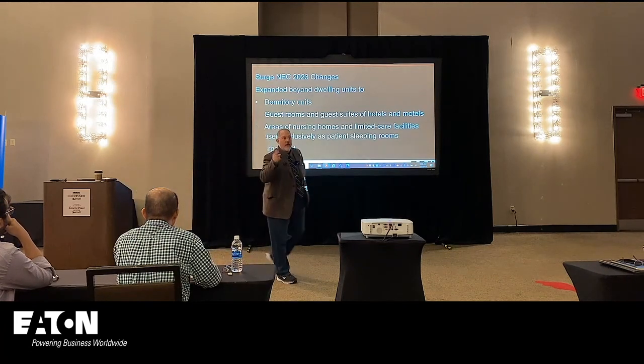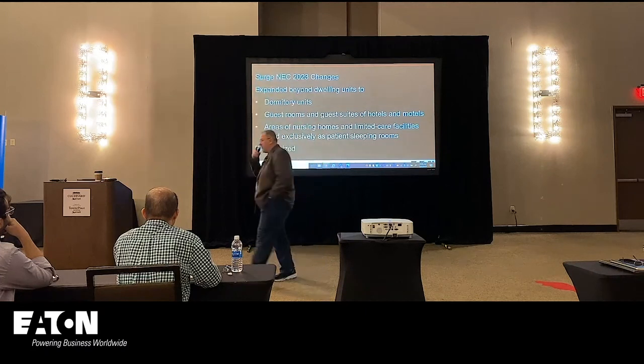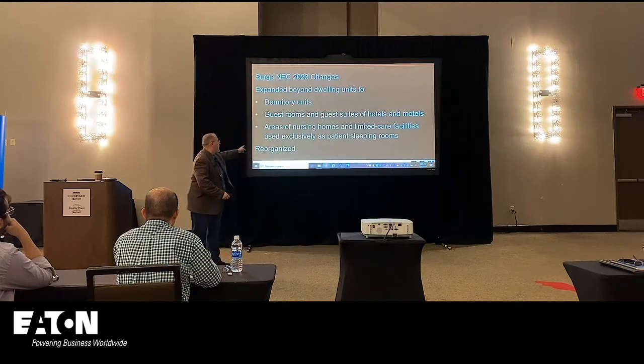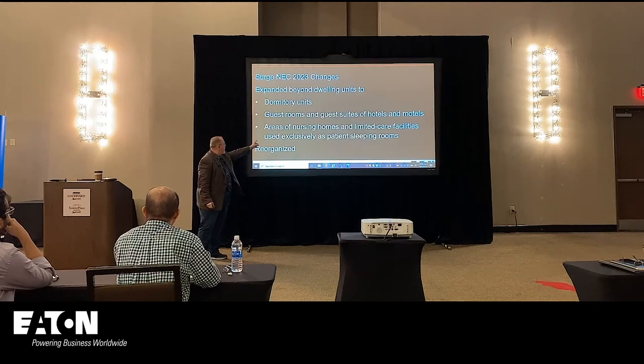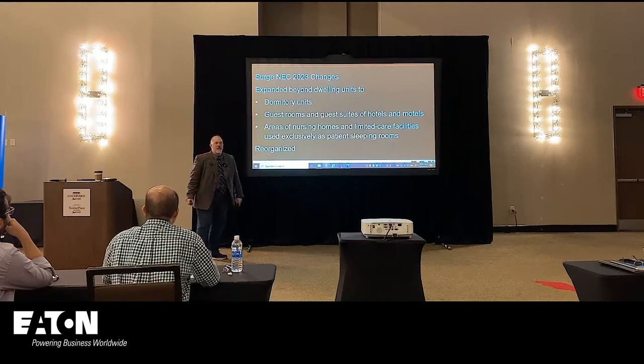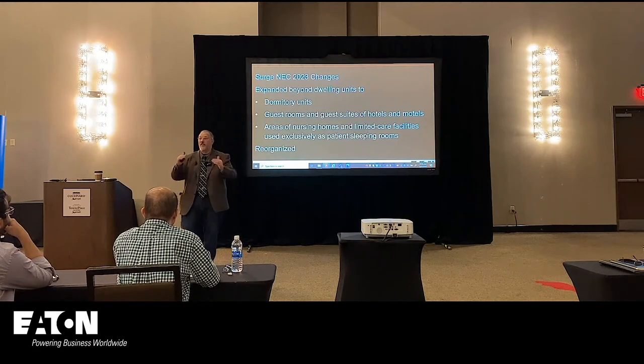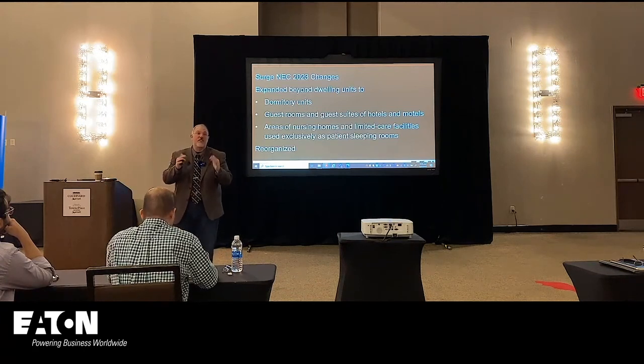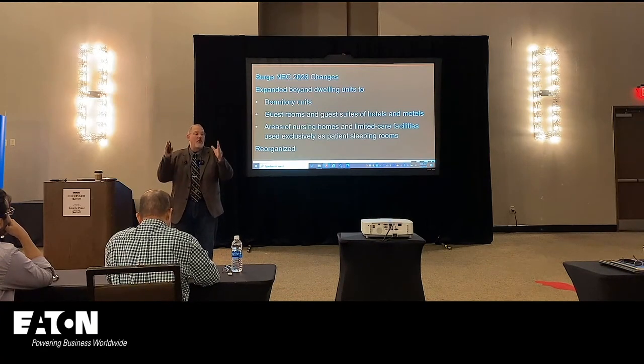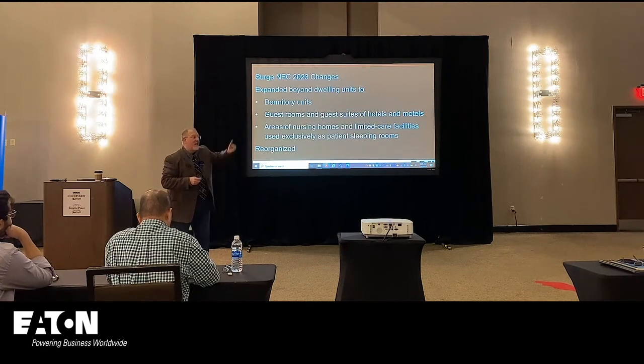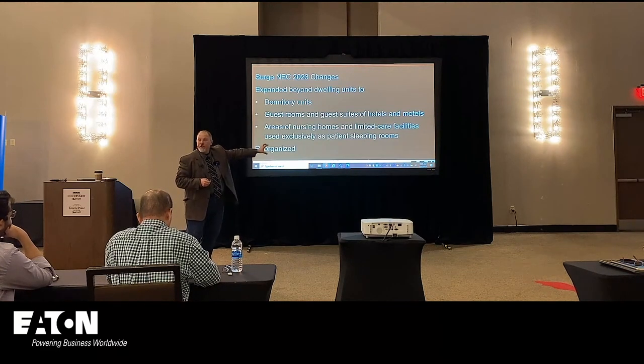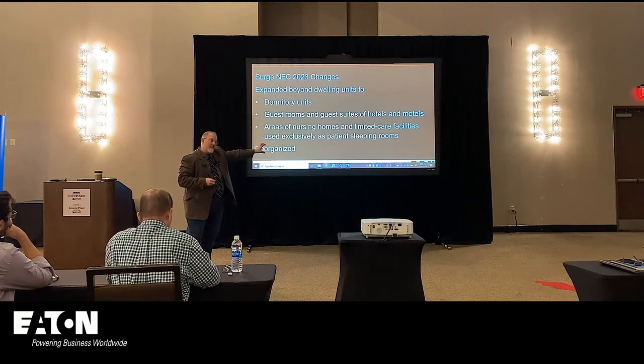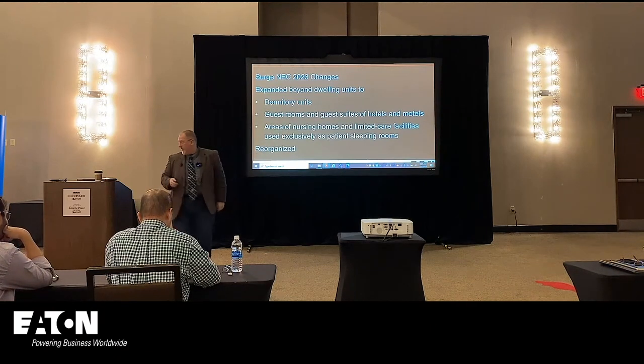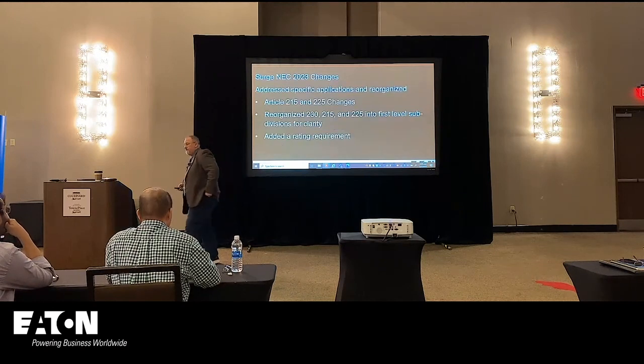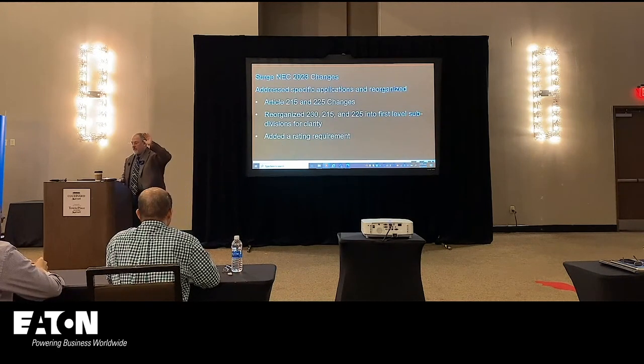All right, so in the healthcare applications, some healthcare people might say, wait a second, you're stepping on the toes of Article 517 with regard to nursing homes and limited care facilities. But if you look at the exceptions, there is a section in Article 517 that says the branch circuit requirements are not covered in 517 for those applications. So that language is exactly extracted basic text from Article 517, that specific section. And we already talked about 215 and 225, and we reorganized 230.